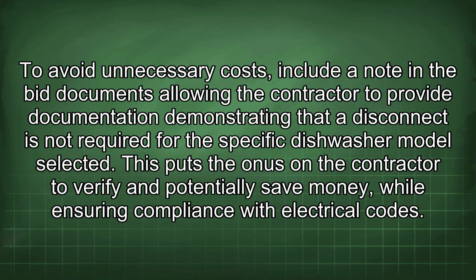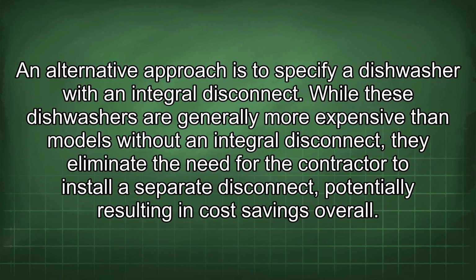To avoid unnecessary costs, include a note in the bid documents allowing the contractor to provide documentation demonstrating that the disconnect is not required for the specific dishwasher model selected. This puts the onus on the contractor to verify and potentially save money while ensuring compliance with electrical codes. An alternative approach is to specify a dishwasher with an integral disconnect. While these dishwashers are generally more expensive than models without an integral disconnect, they eliminate the need for the contractor to install a separate disconnect, potentially resulting in cost savings overall.